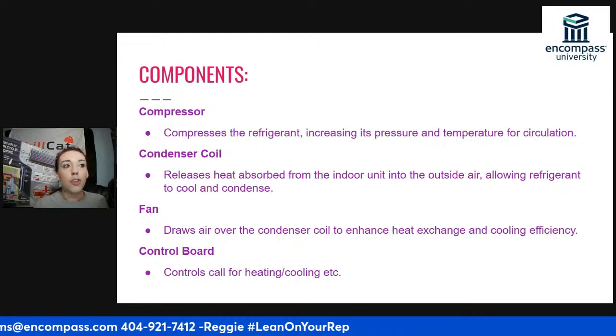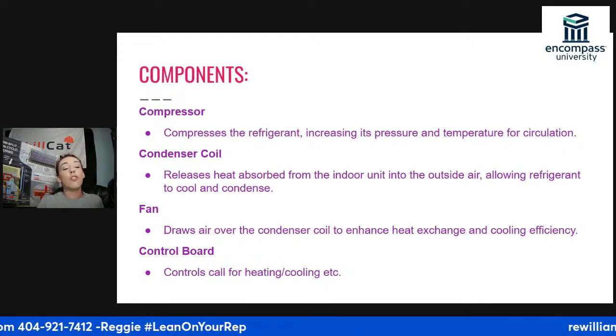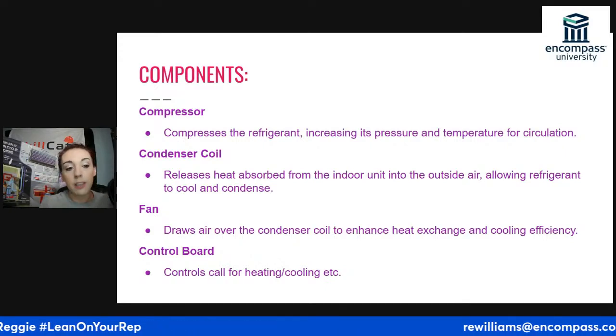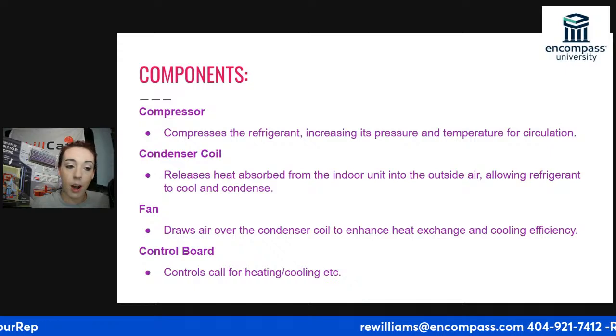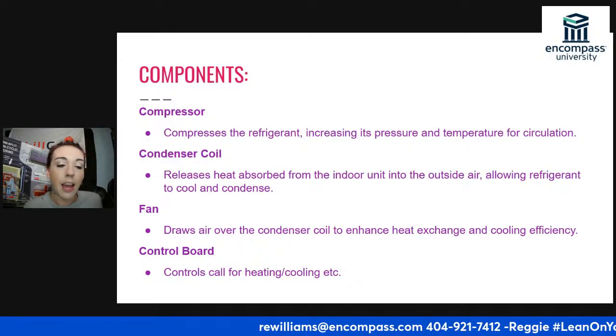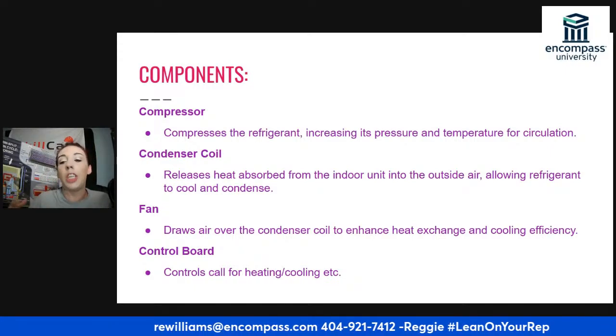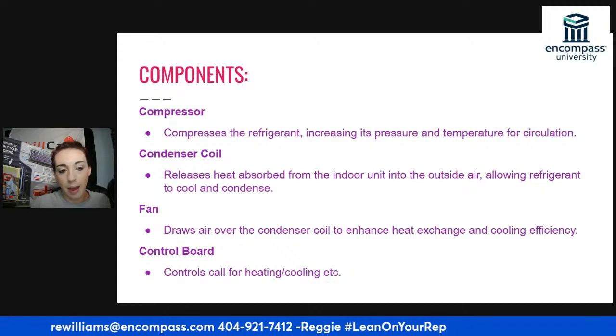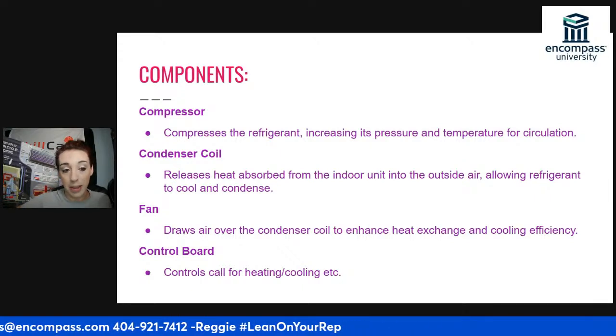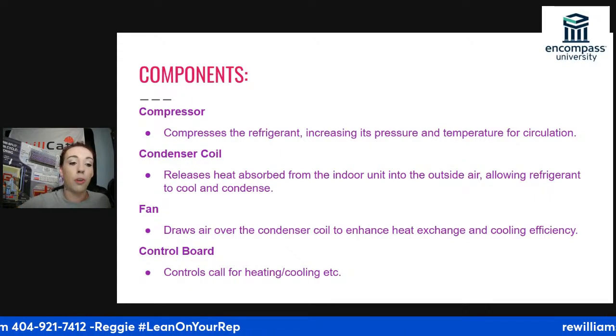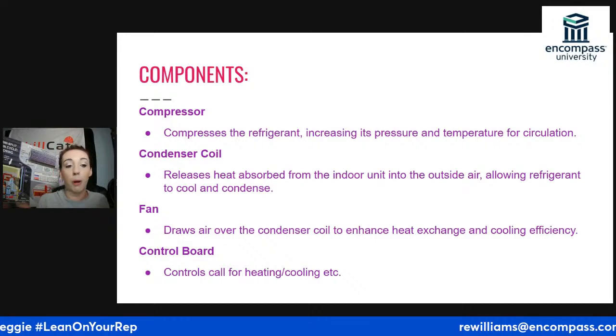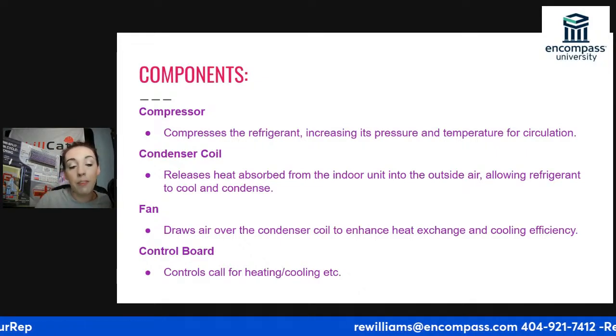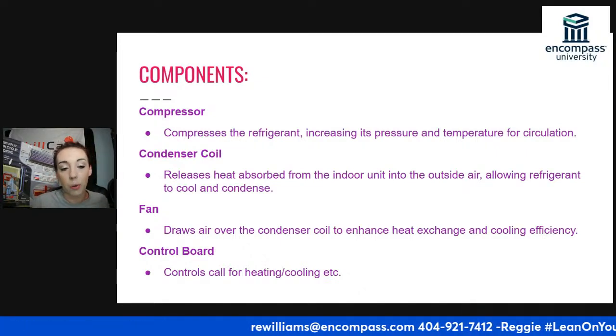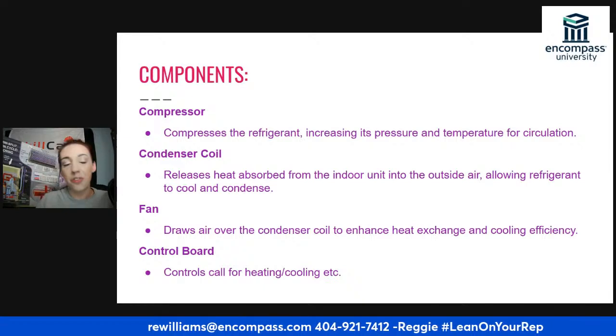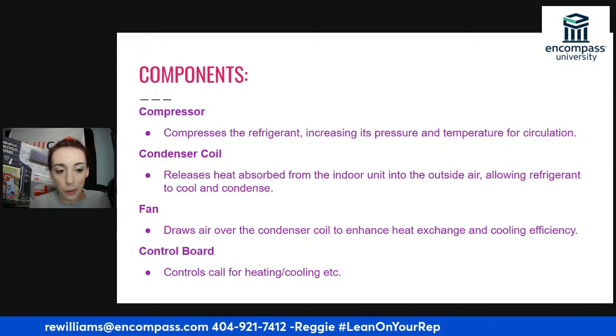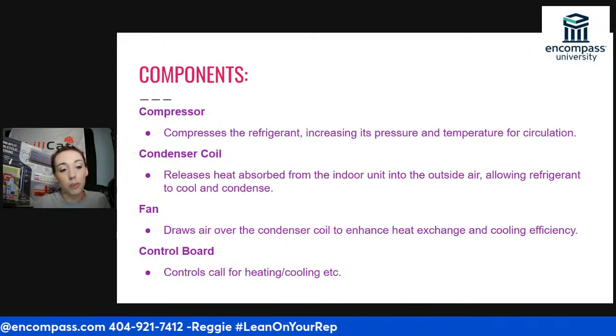Right. So when it is extremely hot outside, mini splits specifically have a very hard time rejecting the heat. And when you hear rejecting heat, what we're talking about is the heat from the indoor space that is brought out to the outdoor condenser and then is supposed to be rejected into the air. But if the air that you're removing from the space, so let's start here. And just for those of you who don't know, which most of you I'm sure do, and I'm not trying to dumb it down at all, I just want to be clear.